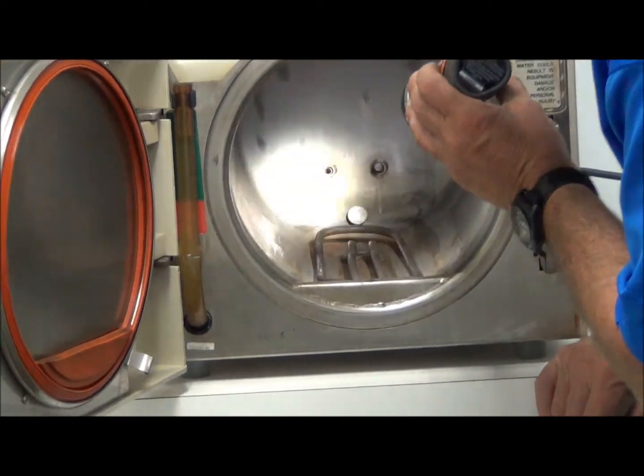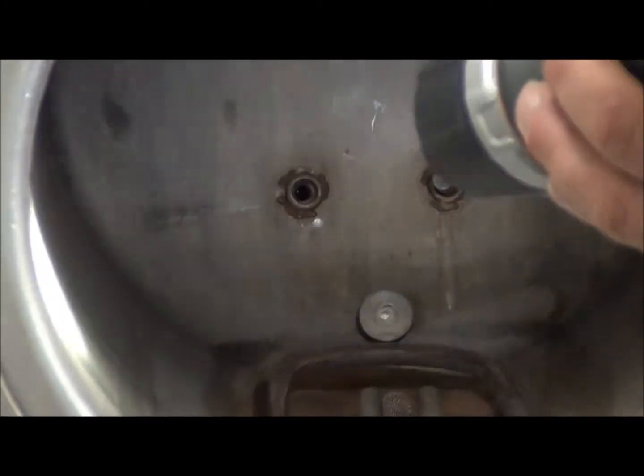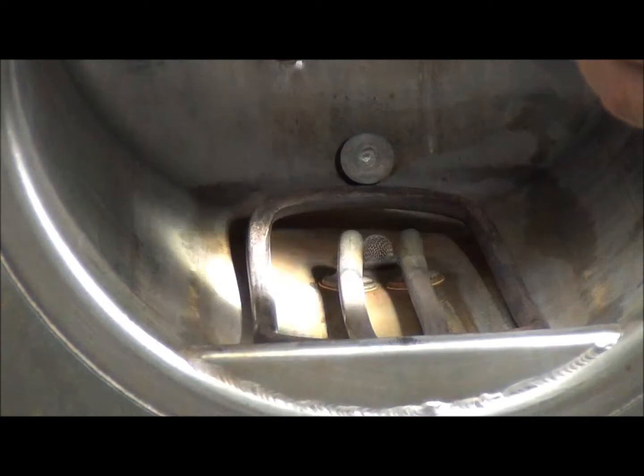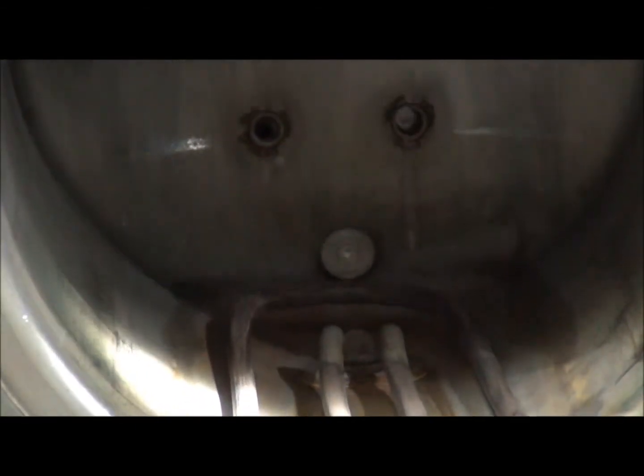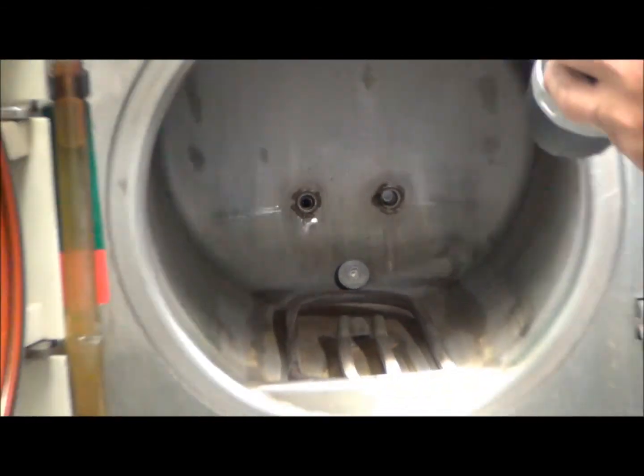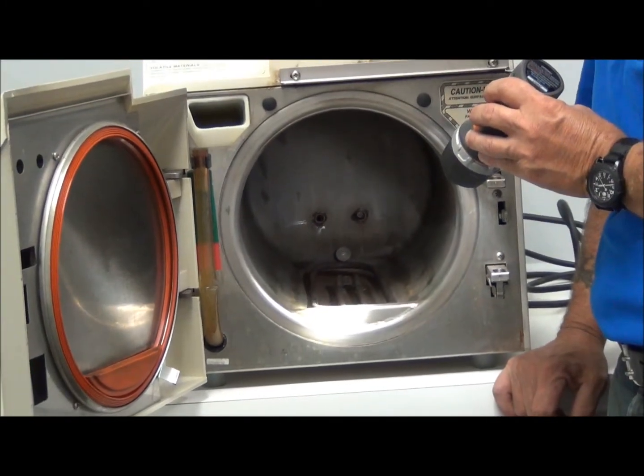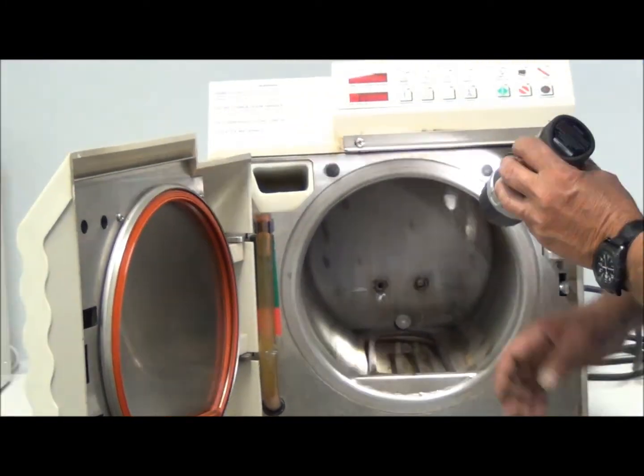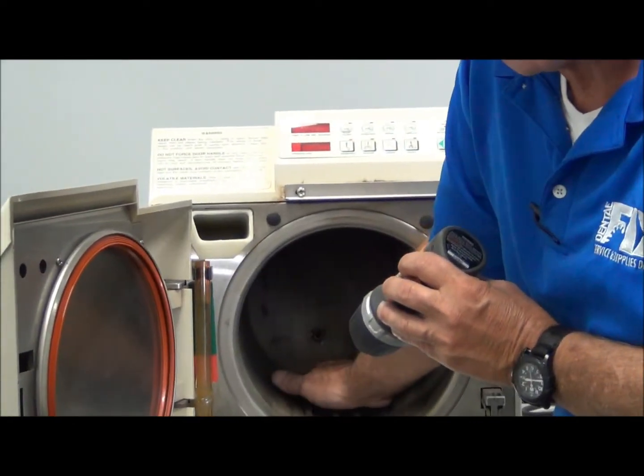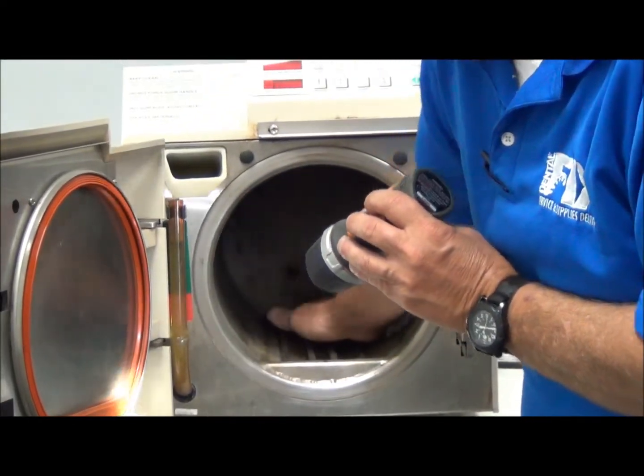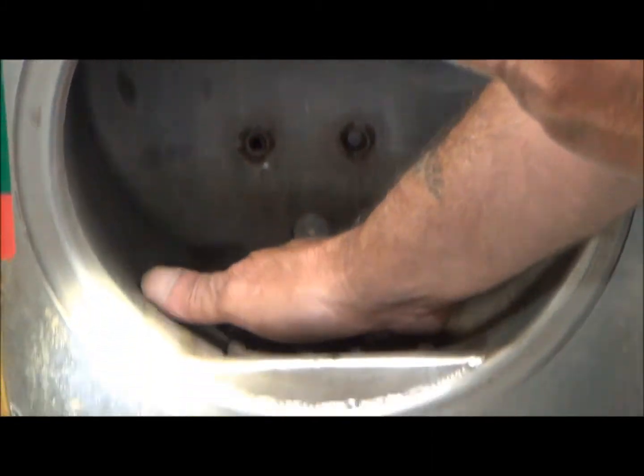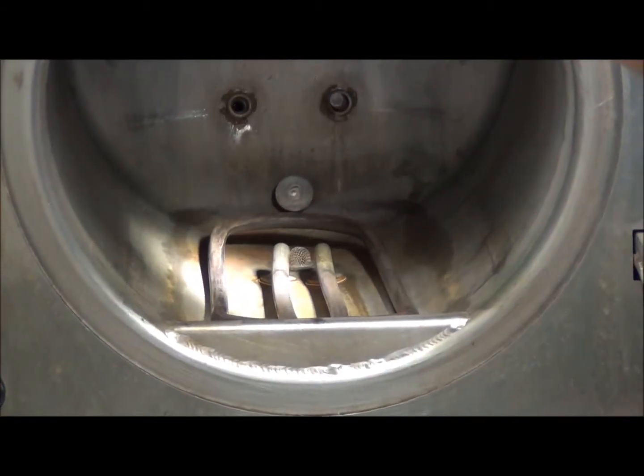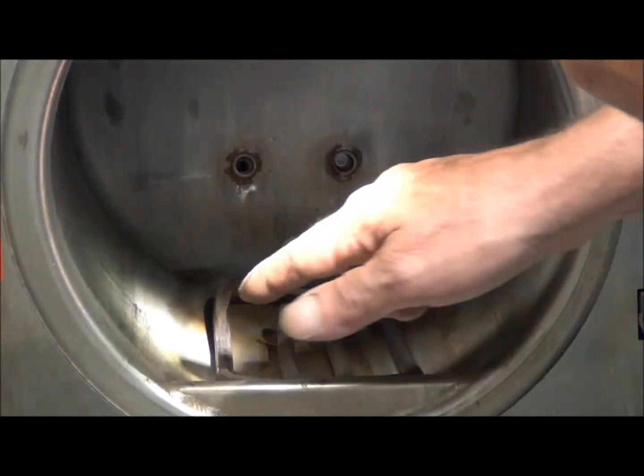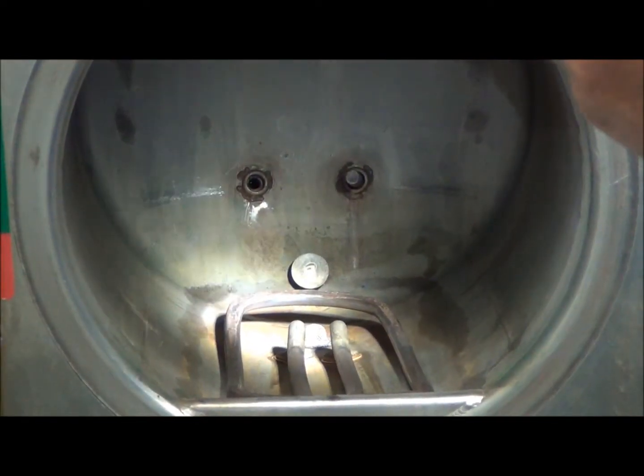We're going to do a visual inspection of the chamber for rust spots, grittiness, crap, rust, and this looks like a very well and very clean maintained sterilizer. Never recommend a cleaner to a doctor that's not the factory recommended cleaner for the sterilizer, by the way. We'll run our fingers. Now, the sterilizer is cool, bear in mind, okay? We'll run our fingers over the elements. The elements feel smooth. I don't feel any pitting on them. I don't see any rust or any splits, which lets me know the elements are good.